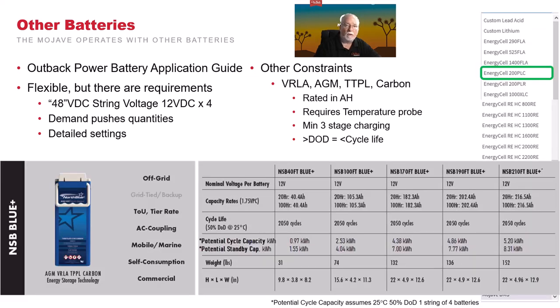When we look at some of our best batteries, you're looking at the NSB Blue batteries. These are a VRLA, AGM, TTPL, nanocarbon. Lots and lots of features in this one. These come in 12-volt batteries. There's going to be 4 in a string. Again, hook as many in parallel as you need to. They're rated in ampere hours. They require a temperature probe. And again, they require a 3-stage charging. The nice thing is that these batteries are very rugged.